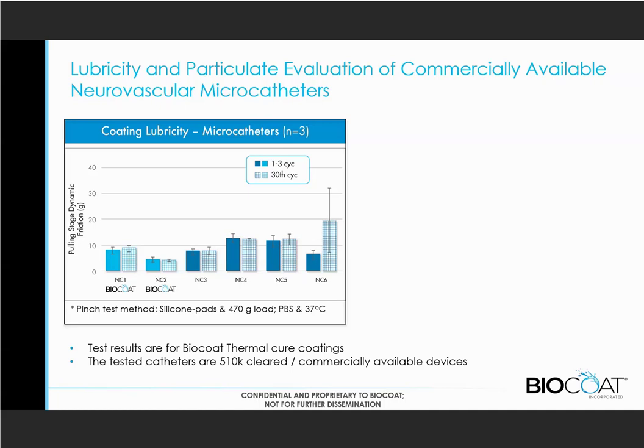This is for the neurovascular catheters, where we're looking at the lubricity. And just to walk you through here, there were 6 different manufacturers and brands of catheters we used. 2 of them we knew were Biocoat customers and had Biocoat coating on them, but the other 4 did not. And so we evaluated all of those and ran this through. We looked at 30 cycles that we were pulling these through this vertical pinch test, and measured both the initial cycles and the 30th cycle. So what you're looking for is low numbers and then not changing much over those 30 cycles.